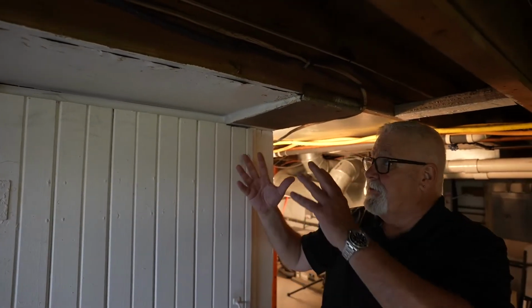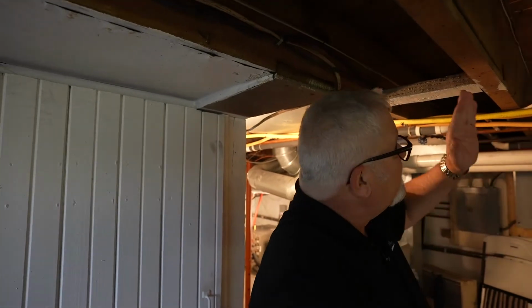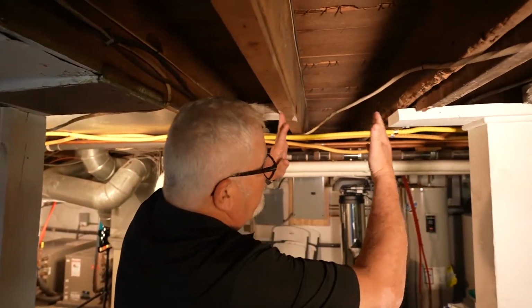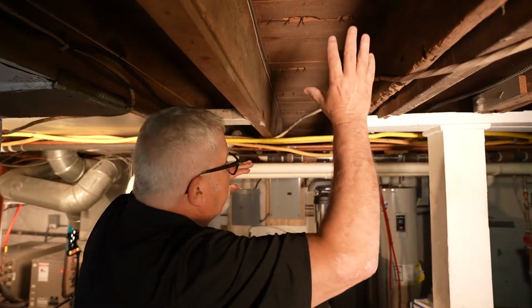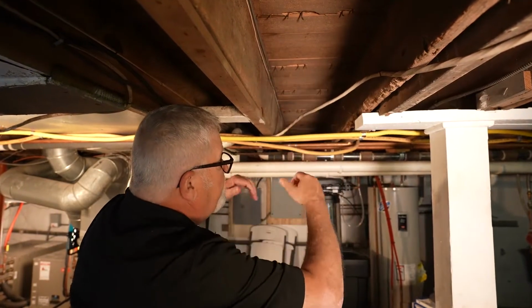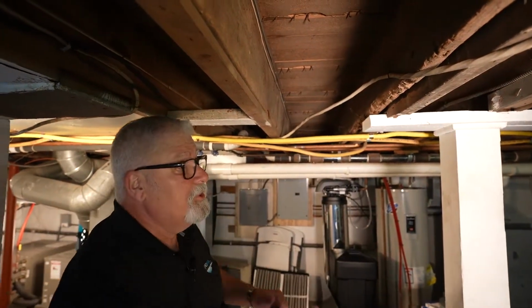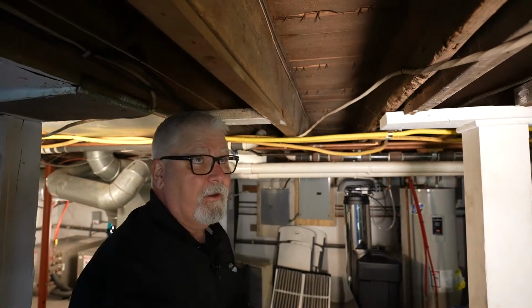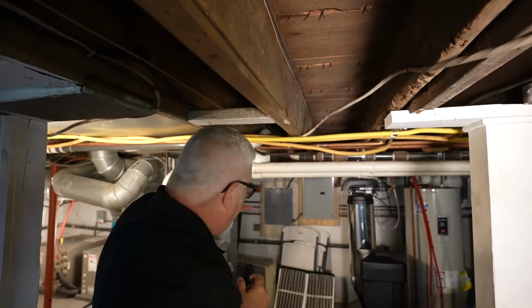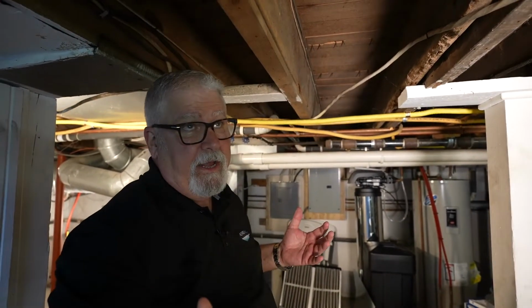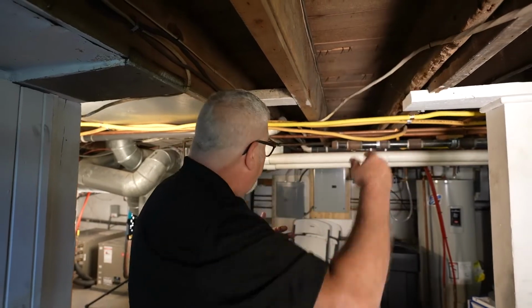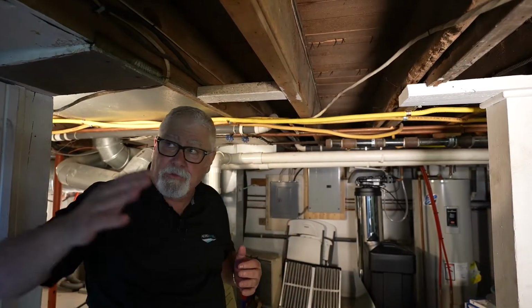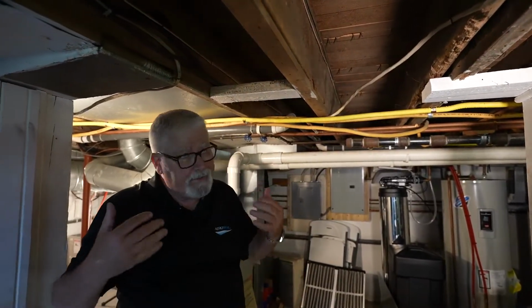But just as an explanation of what they've done here, let's take a look at these floor joists. This is a typical floor joist with the subfloor above me, and all they've done is take a piece of sheet metal and put it across here to direct air back and take it to the return. But as you can see down here in this basement, we've got a lot of wires and a lot of piping, and some of this goes through these returns, which causes other problems.